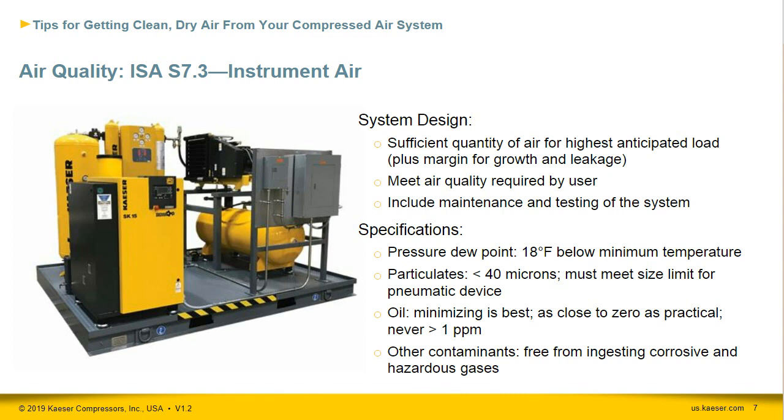Also note that pressure dew point is only 18 degrees Fahrenheit below the minimum operating temperature of the air, which may be a little bit nebulous unless you know your operating temperature. The idea is that if you stay far enough below, you can keep water in the airstream rather than condensing it into the pipes.